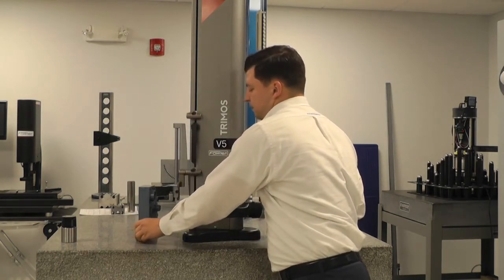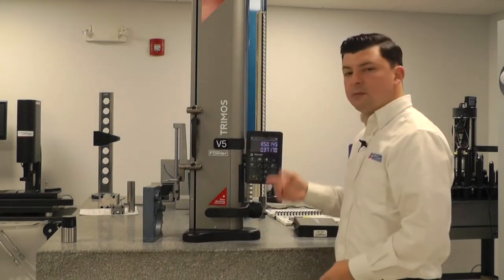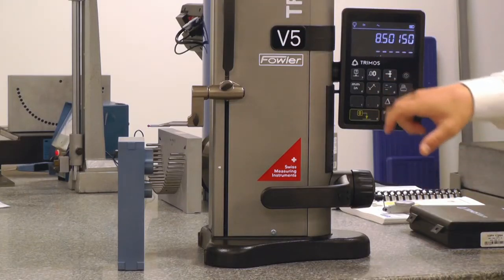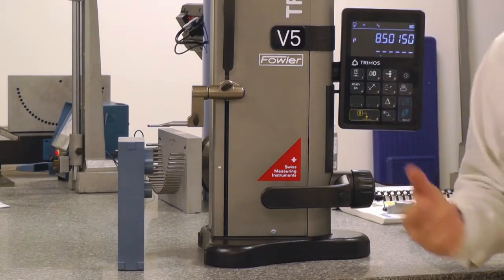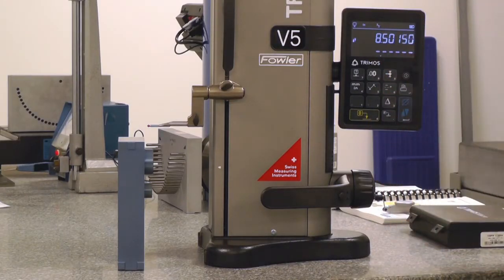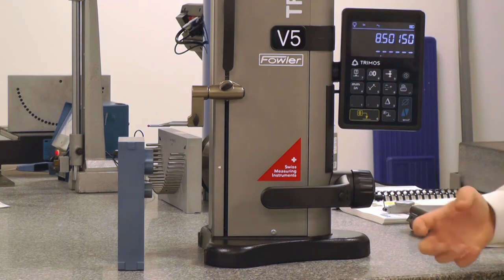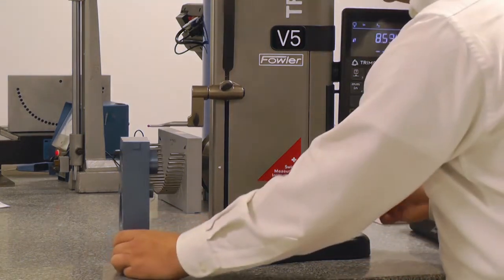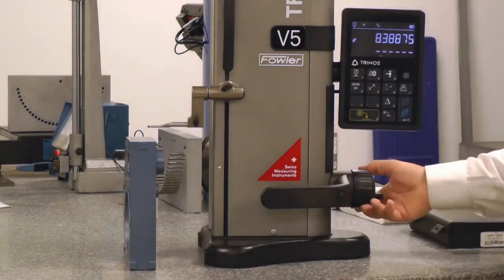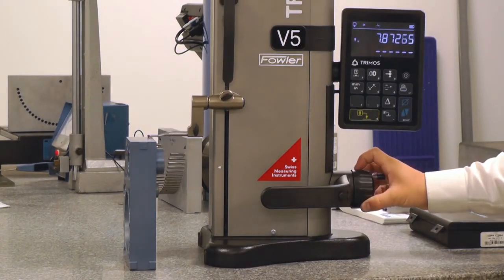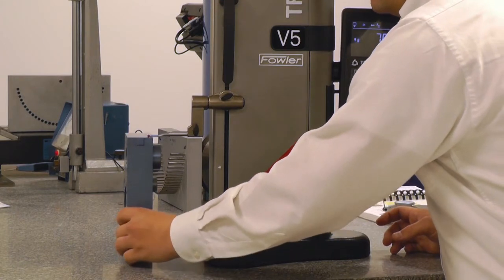From there, so that's our min and that's our max. From there, we have a delta, where we have the top and the bottom of our display. Our arrows are showing the top and the bottom of the sine wave, and this is telling us we're going to take a delta measurement. It's going to give us the difference between the two.